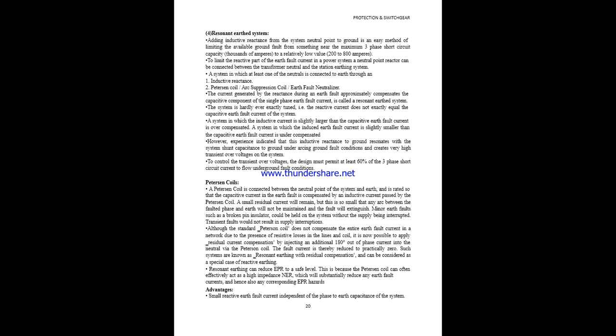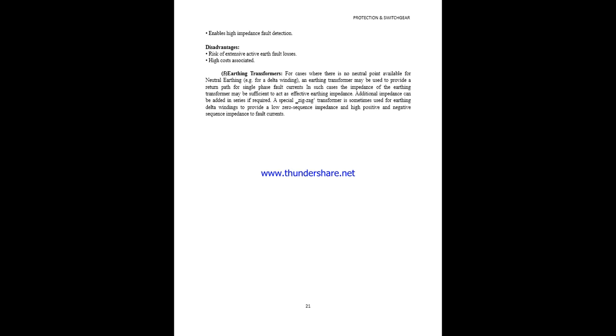While considering the operation, the Petersen coil is connected between the neutral point of the system and the earth and is rated so that the capacitive current in the earth fault is compensated by an inductive current which is passed through the coil. A small residual current will remain, which is very small, so it can be eliminated, and minor earth faults such as a broken pin insulator could be held on the system without the supply being interrupted. So transient faults would not result in supply interruptions. The main advantage is a small reactive earth fault current which is independent of the phase to earth capacitance of the system, and the disadvantage is that the cost is very high.